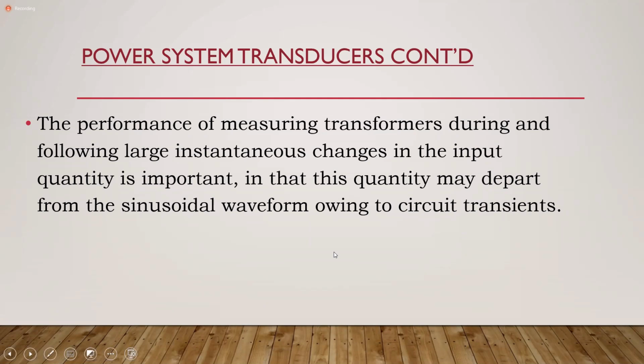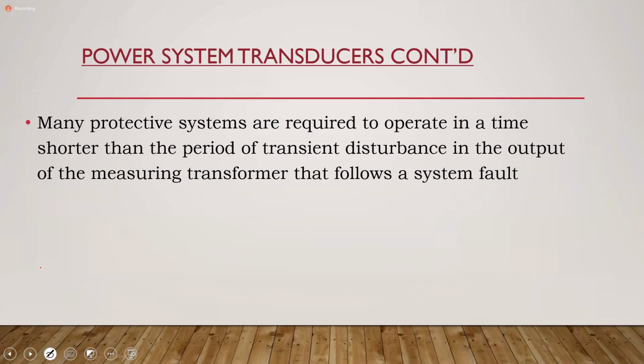Okay. So, as we were saying, the other issue is faithfully producing a replica of what's on the system. The other concern, in terms of your transducer, is that not only must it faithfully represent what's on the system, but your protection system may need to operate much faster, or operate in a time that is shorter than the period of the transient disturbance.